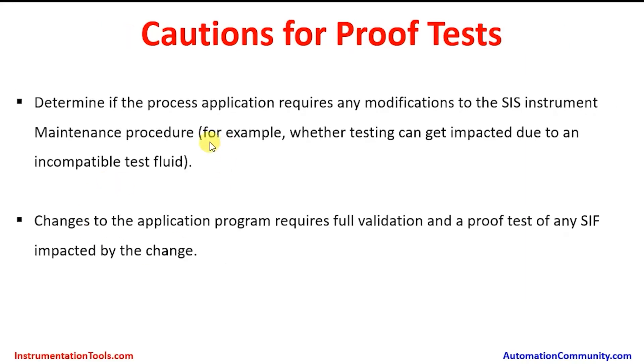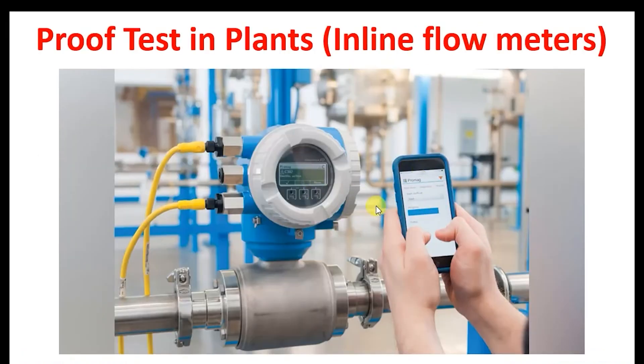Further cautions: determine if the process application requires any modification to the SIS instrument maintenance procedure — for example, whether the testing can be impacted by an incompatible test fluid. Normally, test fluids like nitrogen are used, and it must be ensured these do not get contaminated with the process fluid or gas. Changes to the application program require full validation and a proof test of any SIF impacted by the change. In this picture, an inline flow meter is being tested and adjusted for parameters and configuration.